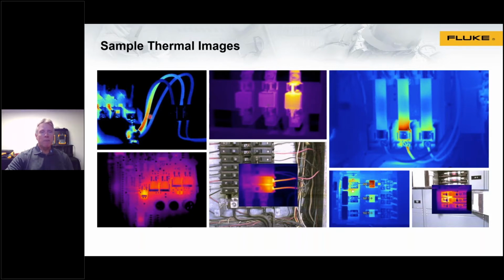That pattern is very symptomatic of a loose connection or a corroded connection. You can see overheated components on printed circuit boards, apparent overloading. If this were a balanced three-phase scenario, this looks like this C phase or L3 looks much hotter than the other two phases. So that could be an example of an overload or some load condition. But at the very least, it's pointing out something that needs attention, as are all these images.